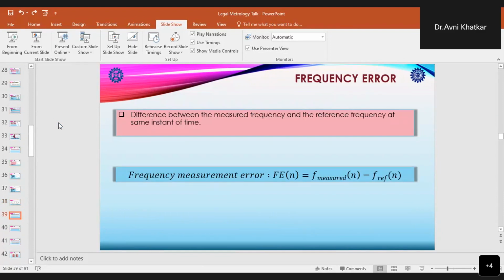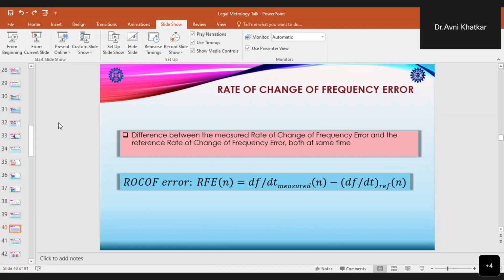After total vector error, next is frequency error. Frequency error is nothing but the difference between the measured frequency and the reference frequency, both measured at the same instant of time. Mathematically, it is the difference between the measured and the reference frequency measurements. The next error that comes into the picture is the rate of change of frequency error. It is nothing but the difference between the measured rate of change of frequency and the reference rate of change of frequency, both measured at the same instant of time.